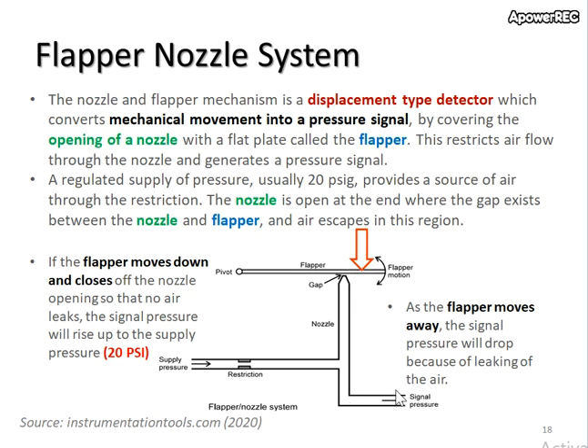Here we have the signal pressure. The nozzle and flapper mechanism is a displacement-type detector which converts mechanical movement into pressure signals. It is achieved by covering the opening of a nozzle with a flat plate called a flapper. This restricts air flow through the nozzle and generates a pressure signal. A regulated supply pressure, usually 20 psig, provides a source of air through the restriction.